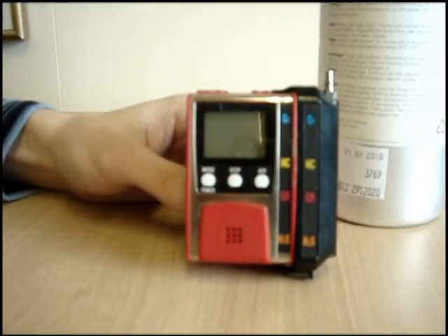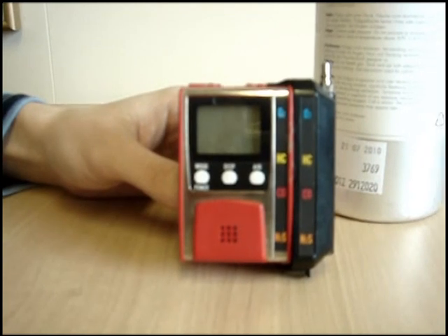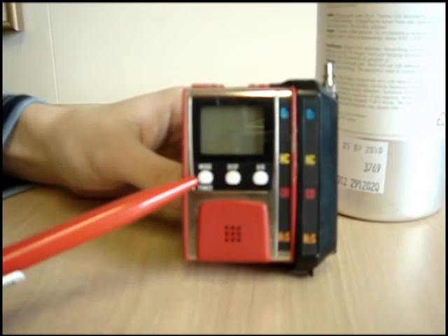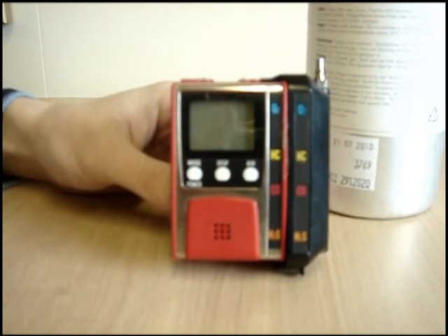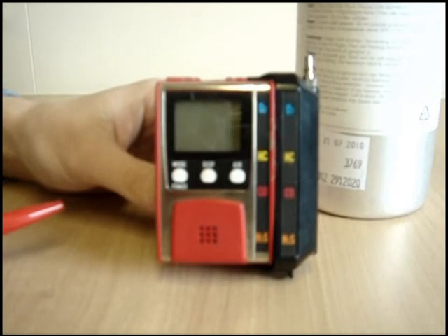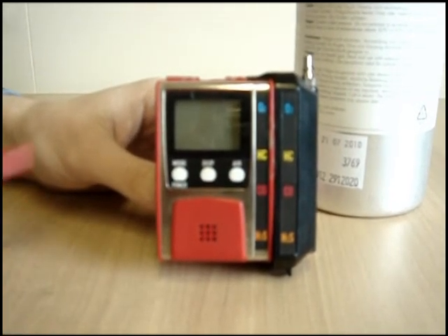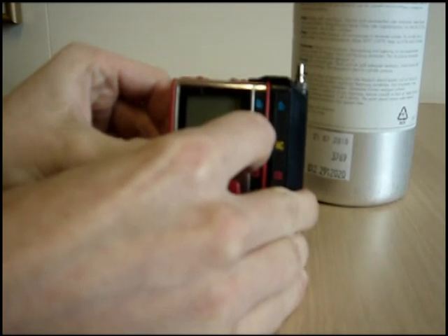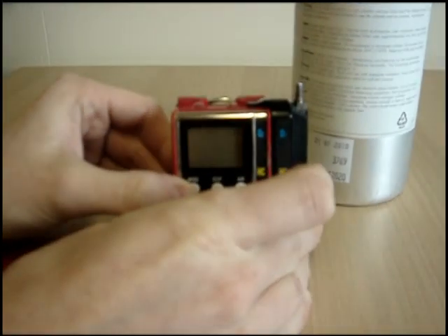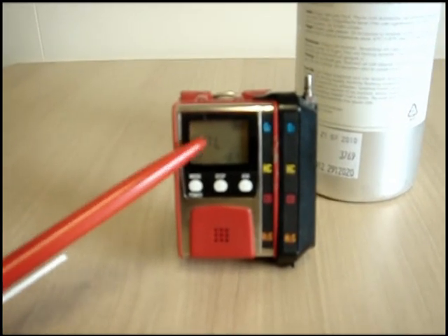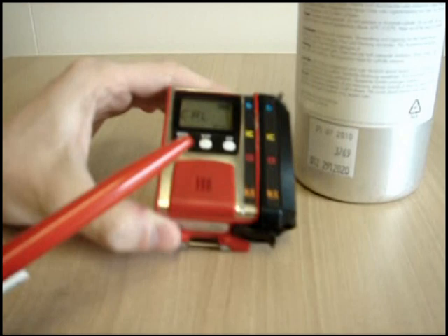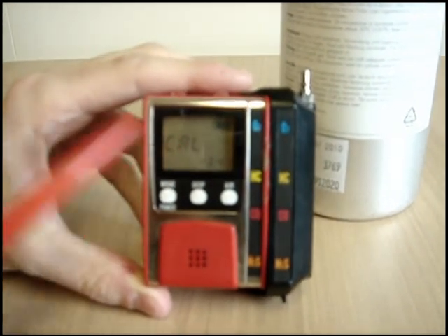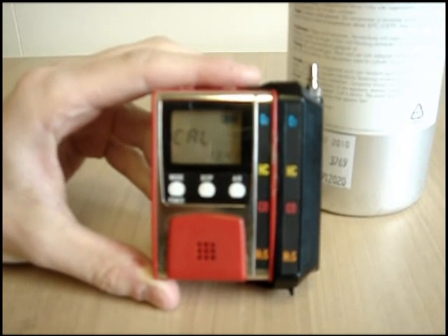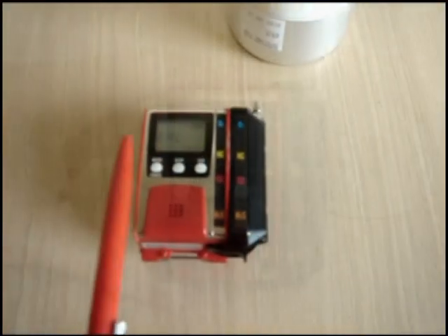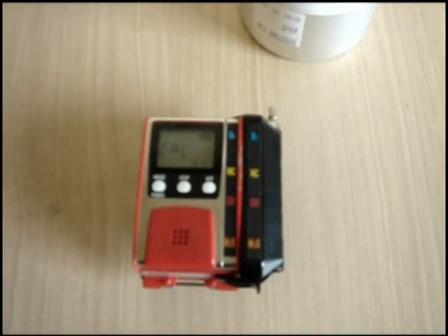To enter the calibration mode on the GX 2001, you have to push the air button and power button simultaneously until you have the light and the beep signal, after which you can release the air button and the display will show calibration mode. You can see on the display the wording CAL, which indicates that the device is in calibration mode. When the device is in calibration mode, it is ready to be calibrated.